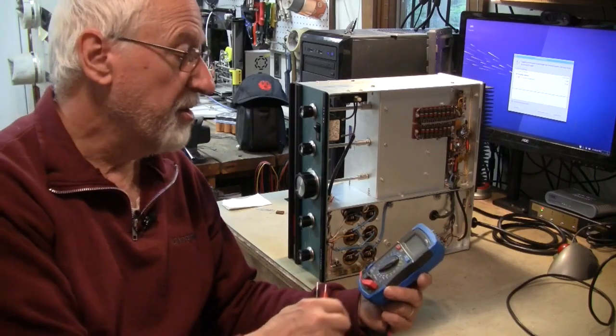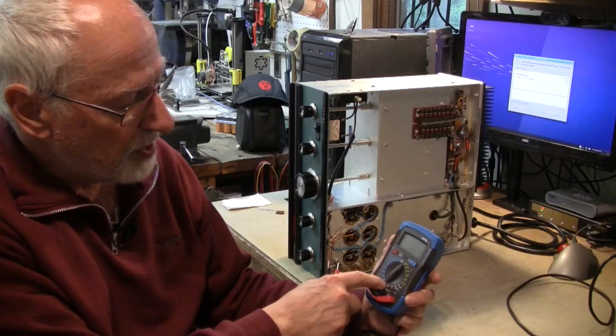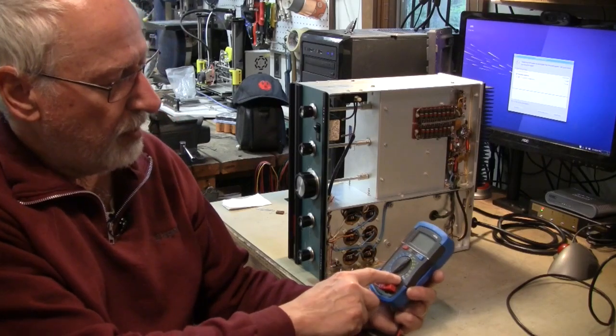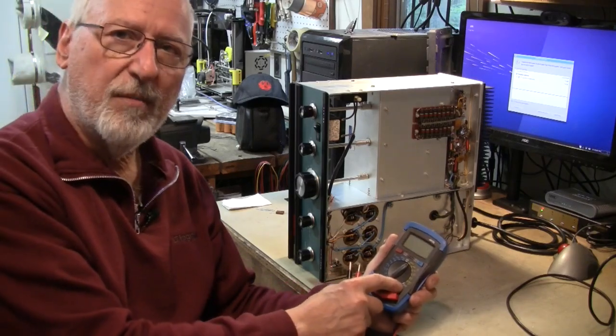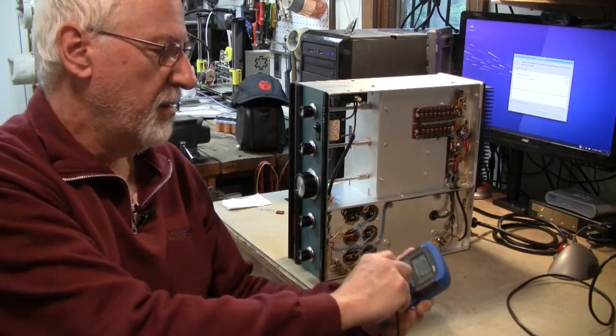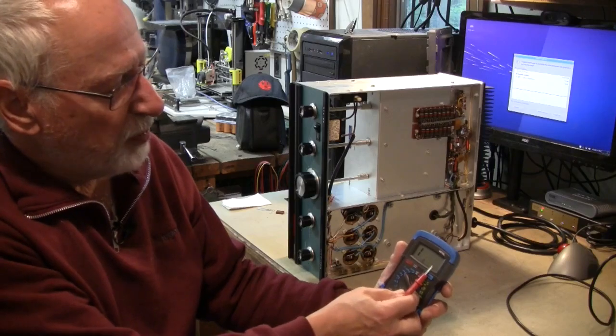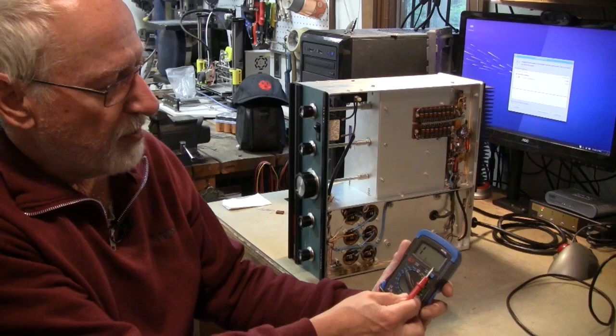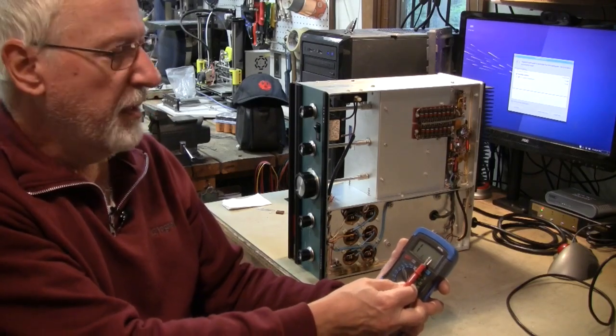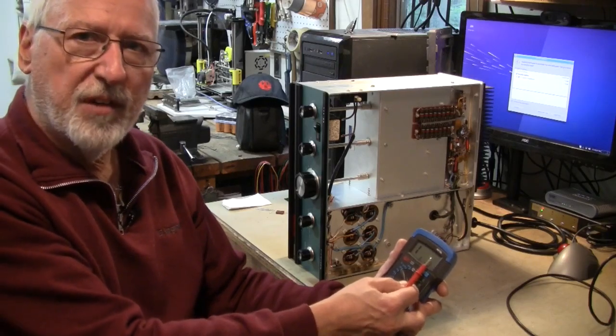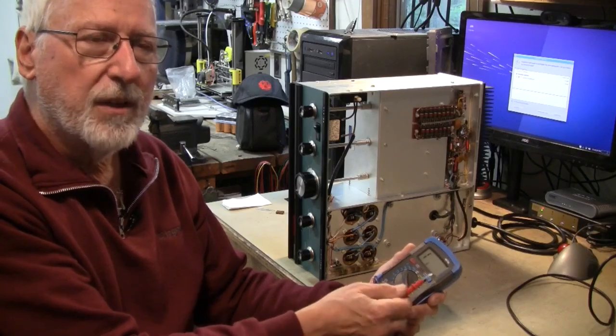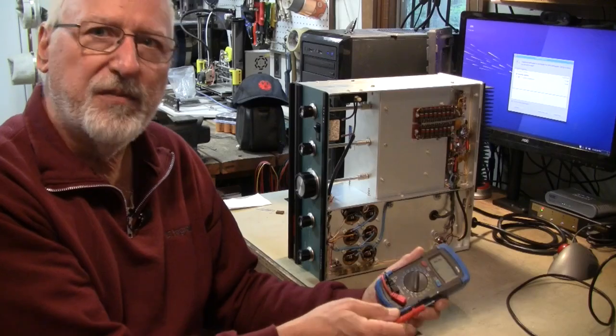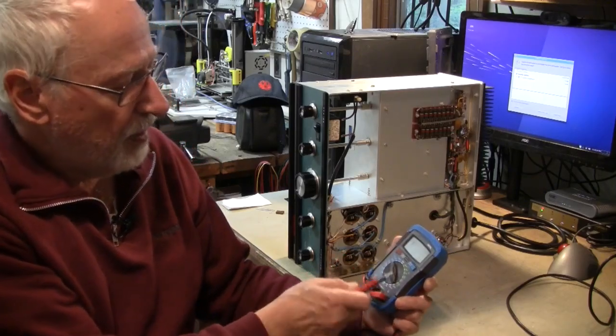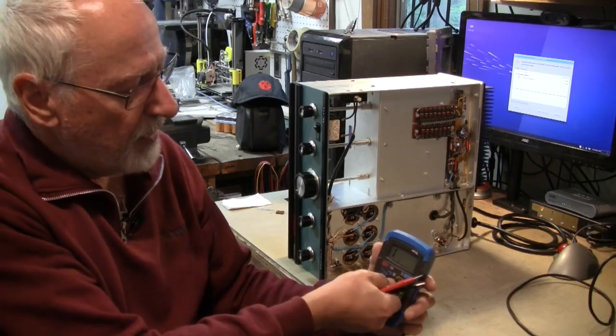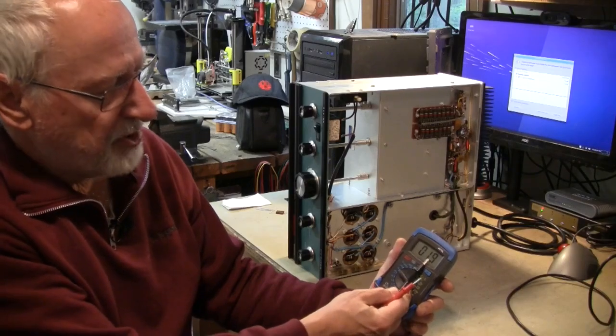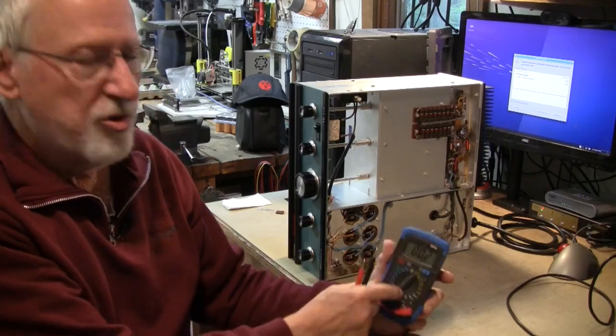It's very handy sometimes. It also measures inductance, with scales of 20 henries, 2 henries, 200 millihenries, and 20 millihenries. Now you might think 20 millihenries as a maximum isn't enough, but there are 2 decimal places beyond that. So 1 decimal place is 10 microhenries, meaning it measures individual digits in increments of 10 microhenries. I can accurately measure inductors as low as maybe 50 to 100 microhenries using this meter. The capacitance maximum is 2000 picofarads, so I can measure capacitors all the way down to 1 picofarad, with a maximum scale of 200 microfarads.